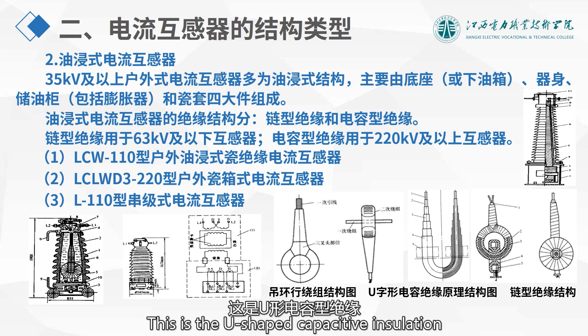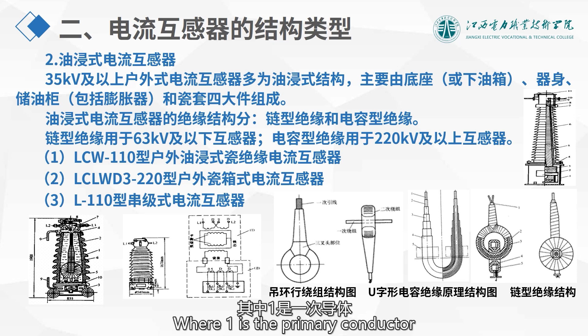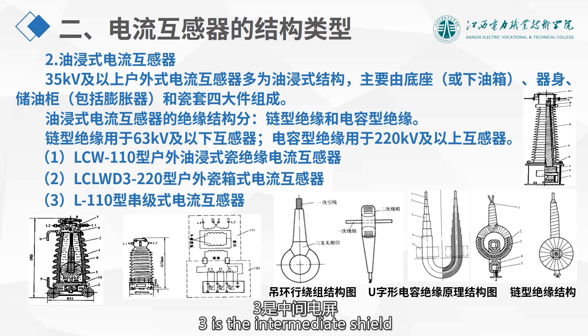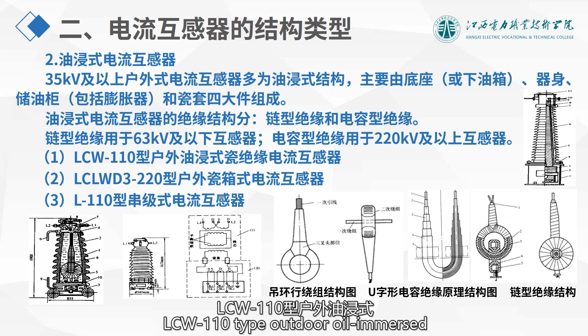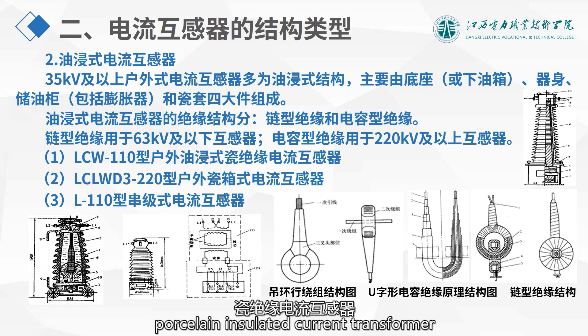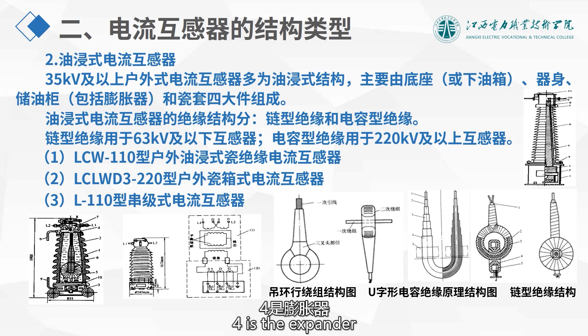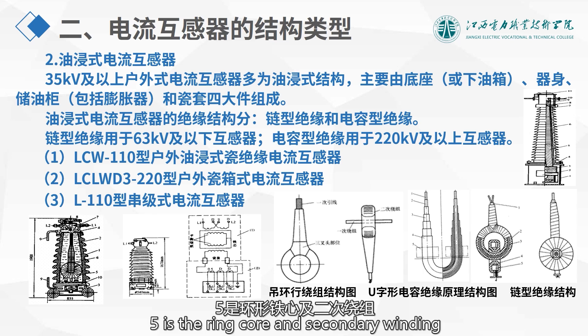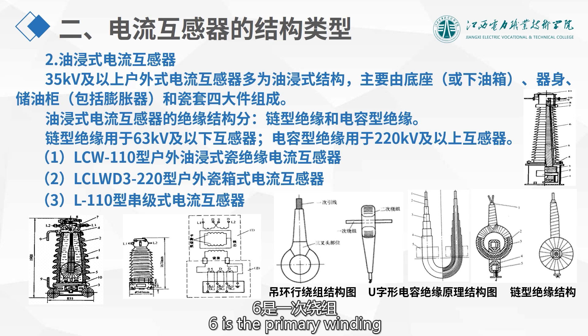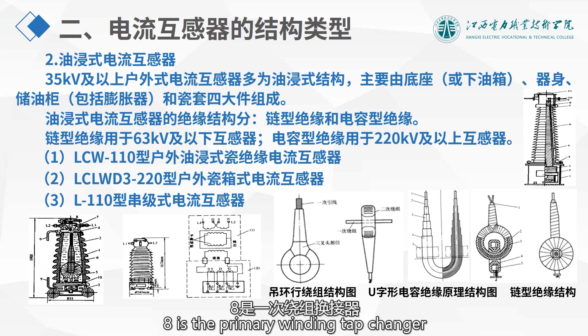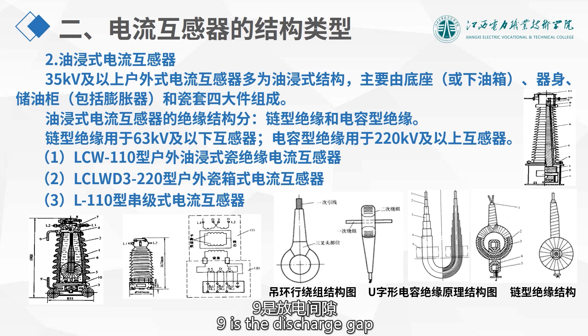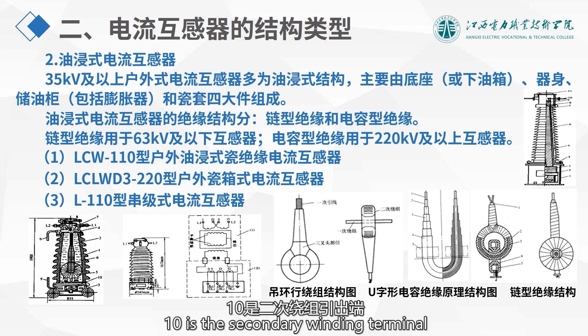This is the U-shape capacitive insulation principle structure diagram, where 1 is the primary conductor, 2 is the high voltage shield, 3 is the intermediate shield, 4 is the ground shield, 5 is the secondary winding, 6 is the primary winding, 7 is the porcelain bushing, 8 is the primary winding tap changer, 9 is the discharge gap, and 10 is the secondary winding terminal.